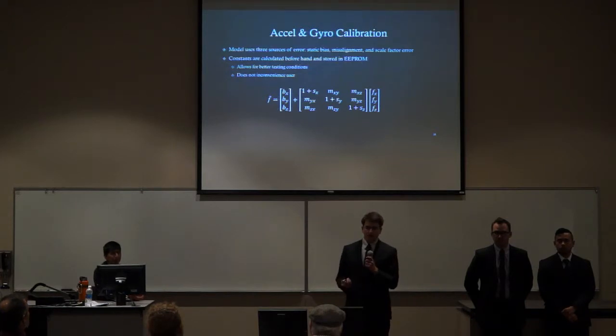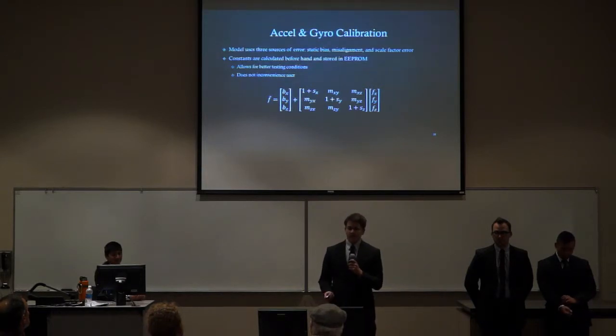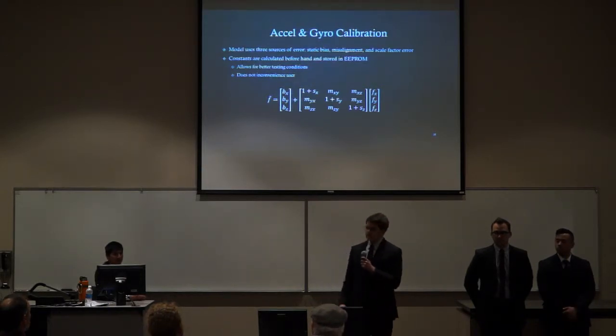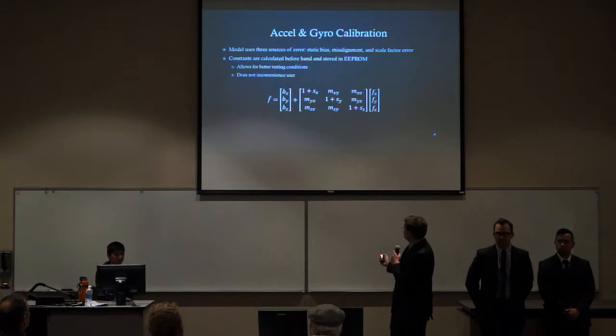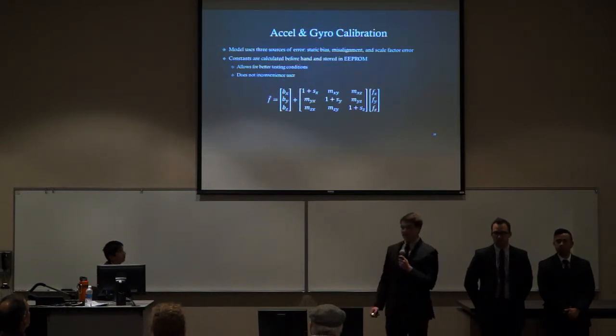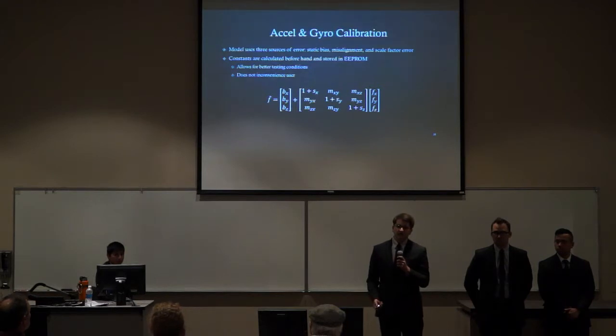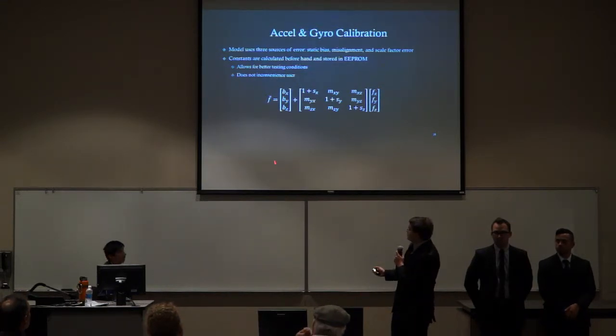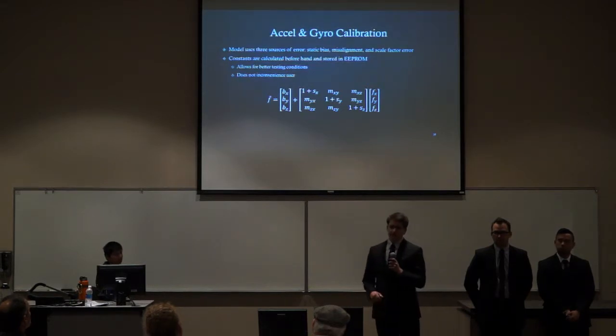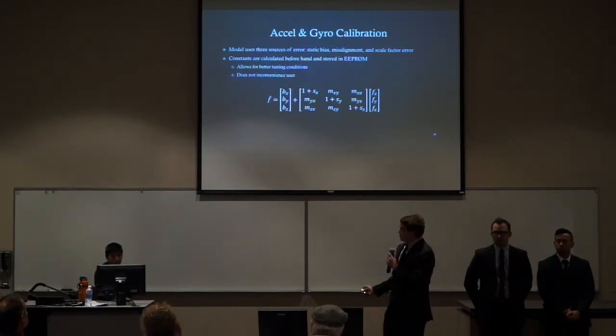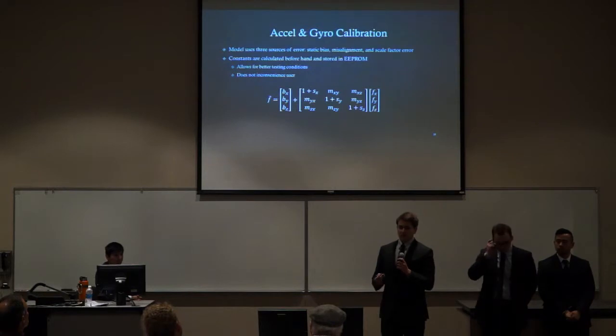And so for our model, we used 3 sources of errors, the ones that were highlighted in red earlier: the static bias, the misalignment, and the scale factor error. This equation down here is the model that we based our calibration off of. Right here, these f sub x, y, and z are the actual values, what we should be reading. So if we're aligned with gravity, we should be reading 1g on the z-axis and nothing on the other two. However, what we actually get is this f with the tilde above it. That is approximately what our sensor is reading. These other matrices are the sources of errors that we are accounting for.